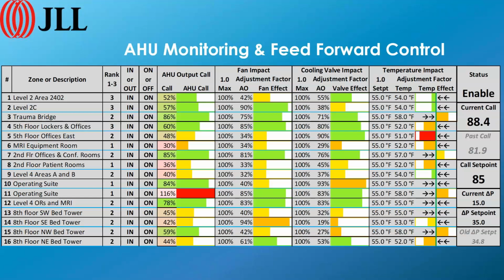But if I have to be really assured that we're going to provide consistent chill water performance for the rest of the building, I just don't worry about it. I do want to make sure I have enough pressure so the chill water valves are functioning correctly. If I'm around 85% to 95%, then my delta P is in control, and whatever the flow is, it's not that I don't care, but it's not something I'm going to worry a lot about. If I'm down at minimum delta P and the valves start to close off, then I'm going to reset the temperature up, but I'm not going to worry about what the flow is in order to do that.